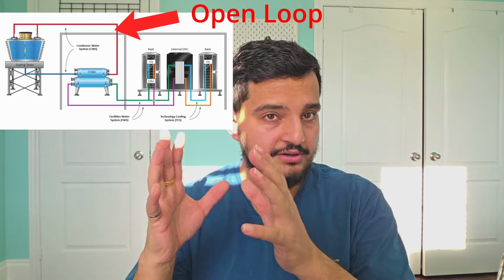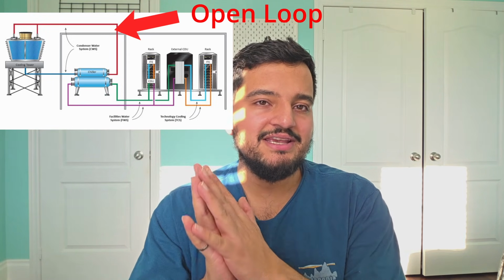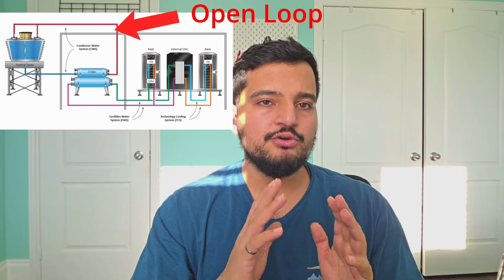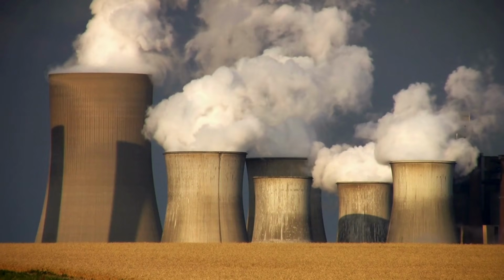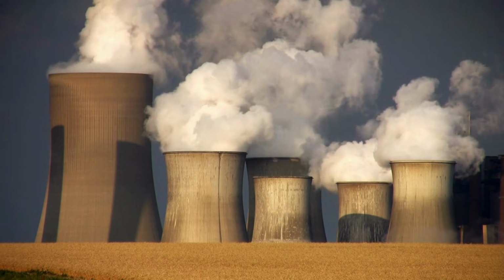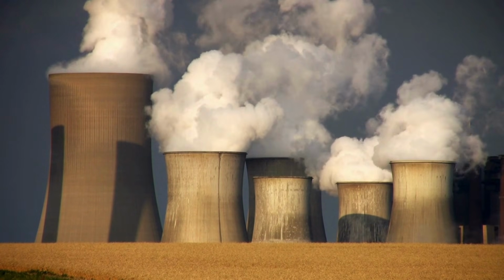However, on the other side of the chiller, the condenser water is actually not a closed loop system. It's an open loop system. So the goal here is to take that heat that the condenser water has collected from all that water inside of the data center and reject it into the atmosphere, so into the ambient air. And that's done through something called a cooling tower. And no, I'm not talking about the giant chimneys you see near nuclear reactors. That's a different type of cooling tower. I'm talking about these things you will see on the top of many high-rises, hospitals, and of course, data centers.